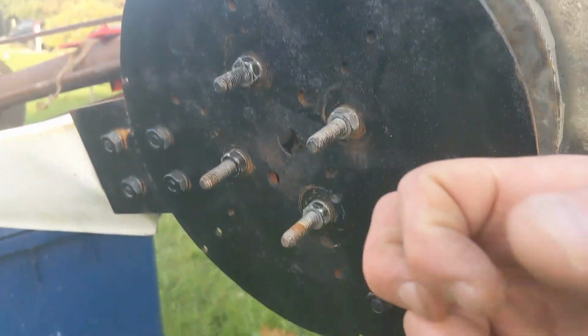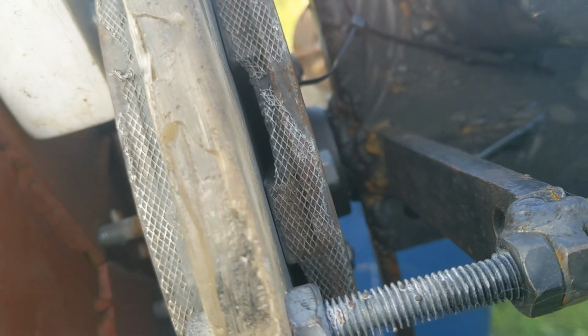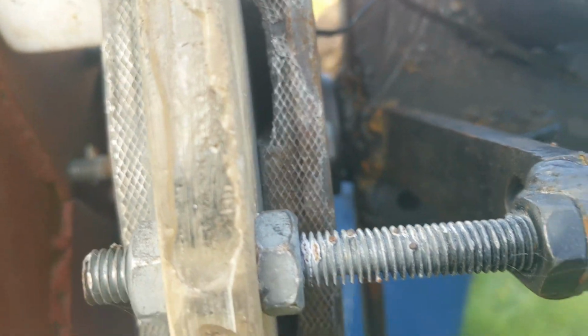So next step is take this off, blades come off with this, that's all good. Take the magnet rotor off, which is a pain. I think one of the jacking bolts has got problems. And God, look at that air gap there, it's tiny, isn't it? Ridiculous.